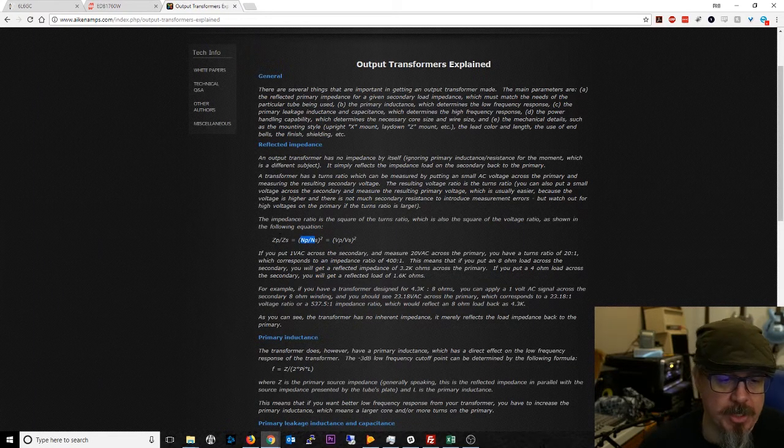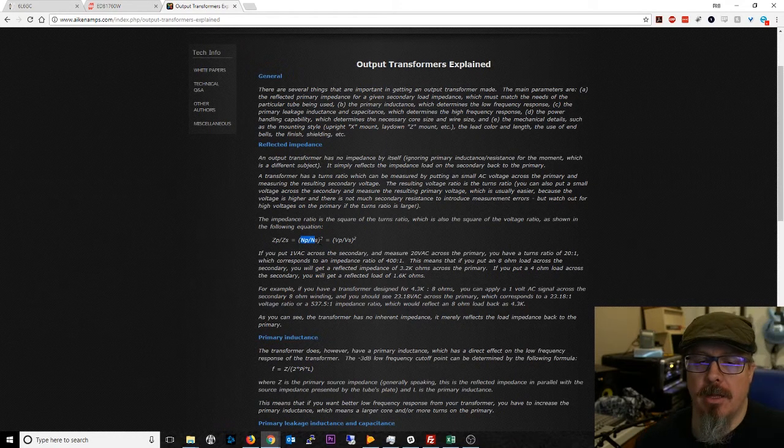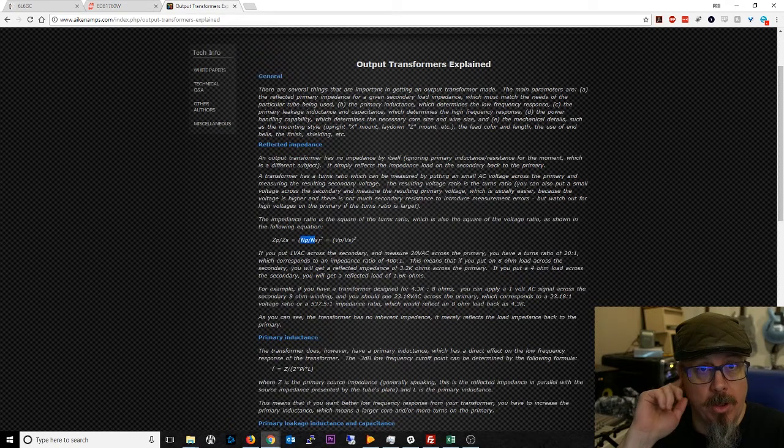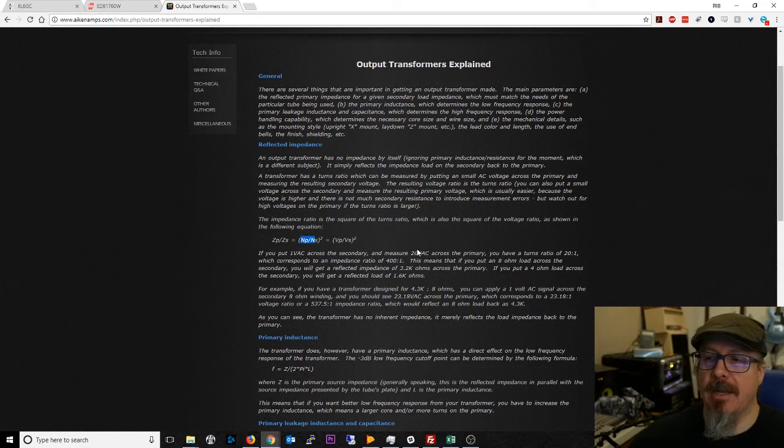Similarly, if you know the voltage rating on one side and you can calculate the other side, you can then make this go backwards. So a classic trick people will use to see what the turns ratio is on a transformer would be to get a variac, hook it up to the transformer on one side, which they wouldn't know what it was, but set it at a very low rating, like say 10 volts. If you've got the primary side, your other side is going to be very low, 1 or 2 volts, and you're fine. But if you've got the right one, that 10 volts might jump up to 200. So you just get, maybe 400, whatever, but you get a multimeter on the opposite side, and you make sure you don't let those leads get close to each other so they can arc.